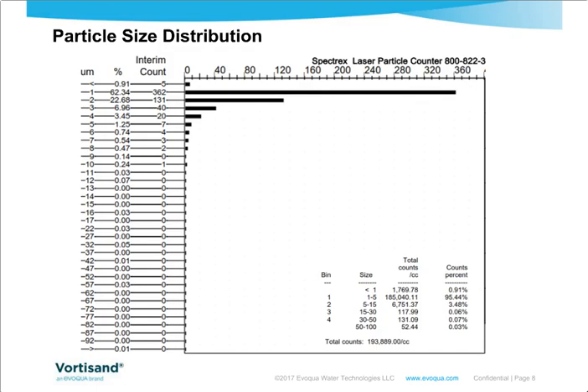Now, particle size: you have those 256 billion particles, and they're not all the same size. There's a distribution of particle sizes. It's important not only to understand the TSS, but to understand the particle size distribution. The industry uses something called laser particle count analysis that can better quantify your water quality, to a higher level of resolution, to identify those small particles.